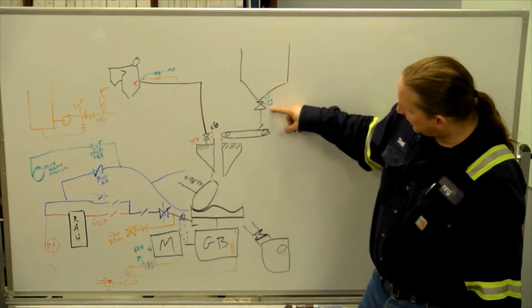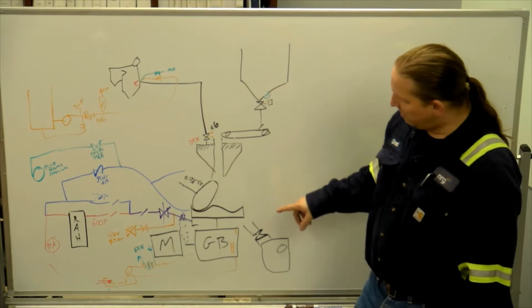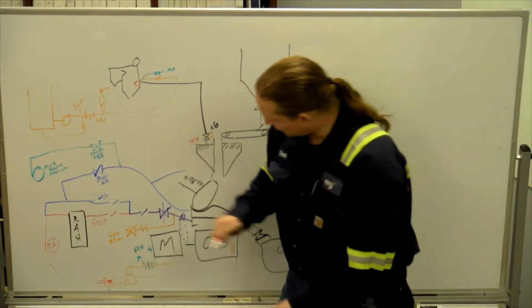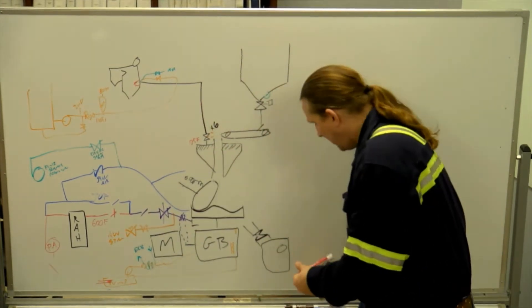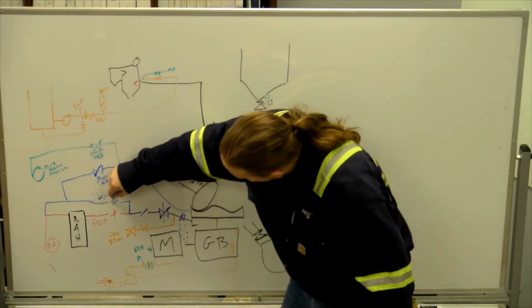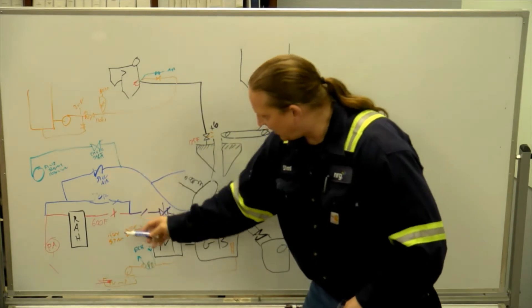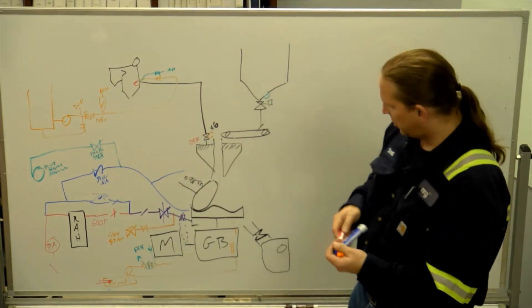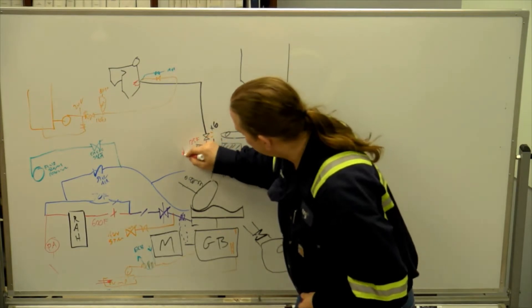Then, the mill speed is going to go to minimum, then we're going to cool off the mill. This guy goes shut, and this guy goes all the way open, and we're putting cold air only into the mill to try and cool this down to 105.